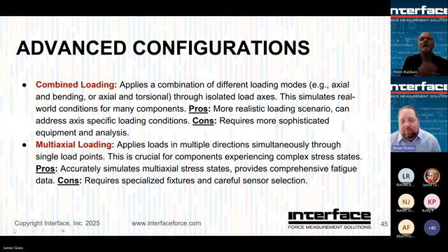Great if you only have a single input force. Real world parts usually see more than that, especially a lot of our aerospace customers are testing components that are seeing forces coming in from all different directions. Again, ideally, we always recommend isolation of those input loads, having actuators aligned with single sensors. Best way to do it.